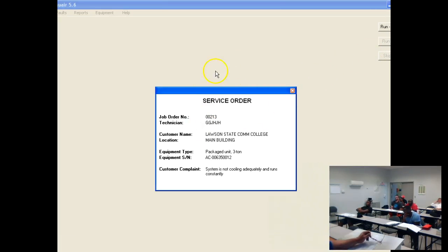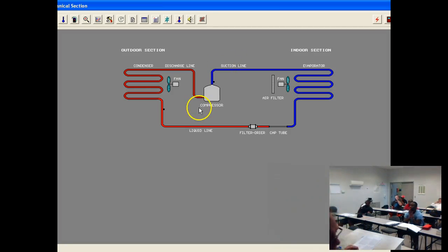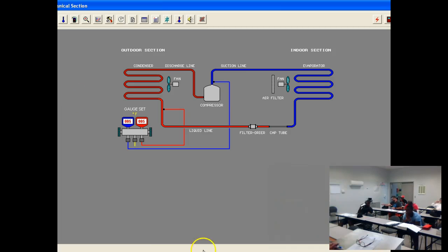Now this fault, I have a service order here. I got a package unit 3-ton AC. System is not adequately cooling and runs constantly. Okay. First thing I can do, what did I tell you? I put my gauges on. Right? I cut my system on. I see both fans are running.